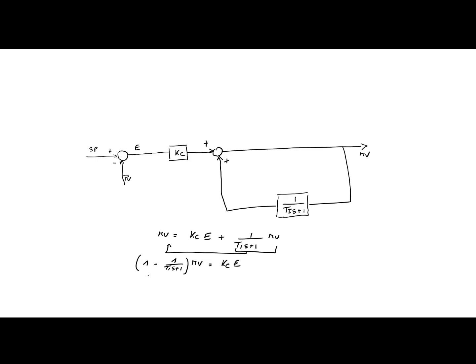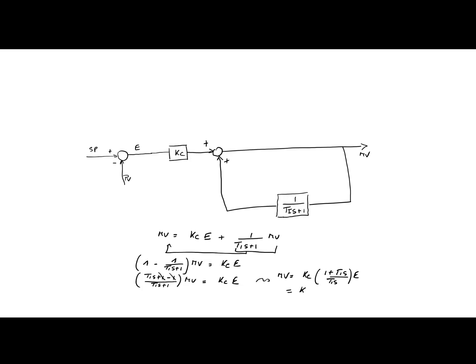MV is equal to Kc times E plus 1 over Ti s plus 1 times MV. I'm going to take this one to the other side, so I'm going to have 1 minus 1 over Ti s plus 1 times MV equals Kc E. MV, I'm going to put that now on the same denominator, so Ti s over Ti s plus 1 times MV is equal to Kc E. This one and this one they cancel out. You see that MV is equal to Kc times 1 plus Ti s over Ti s times E. And this you can rewrite as Kc times 1 plus 1 over Ti s times E. And this is indeed a PI controller.